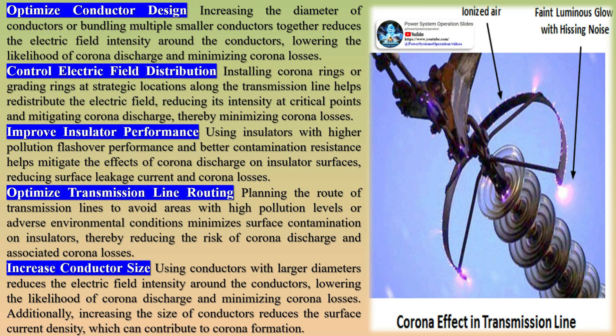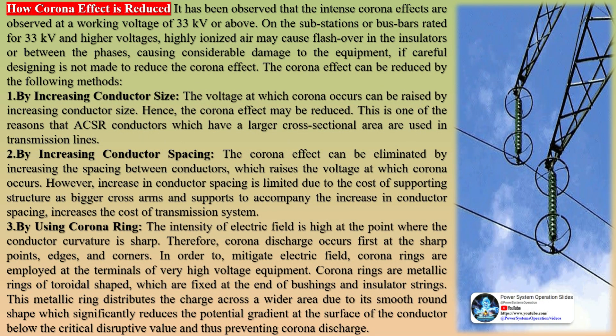Methods for reducing corona losses: corona loss can be reduced by using conductors with large diameters, as increasing the size of the conductor raises the voltage at which corona occurs. Hollow conductors are used to increase the effective diameter of the conductor without using additional material; since corona loss is inversely proportional to the diameter of the conductor, corona loss decreases with an increase in diameter. Bundled conductors, made up of two or more sub-conductors used as a single-phase conductor, and optimized conductor design also help. Installing corona rings or grading rings at strategic locations along the transmission line helps redistribute the electric field, reducing its intensity at critical points and mitigating corona discharge, thereby minimizing corona losses.